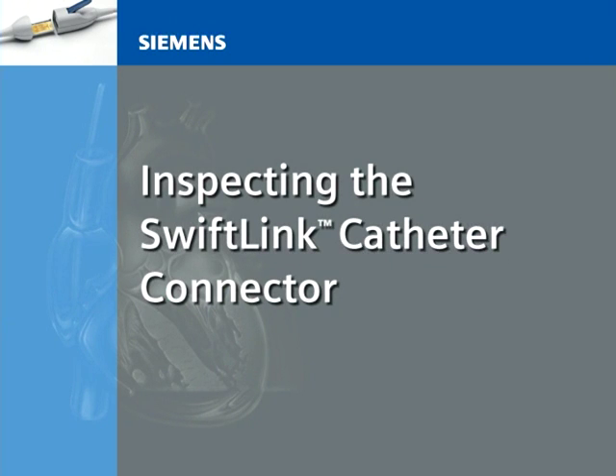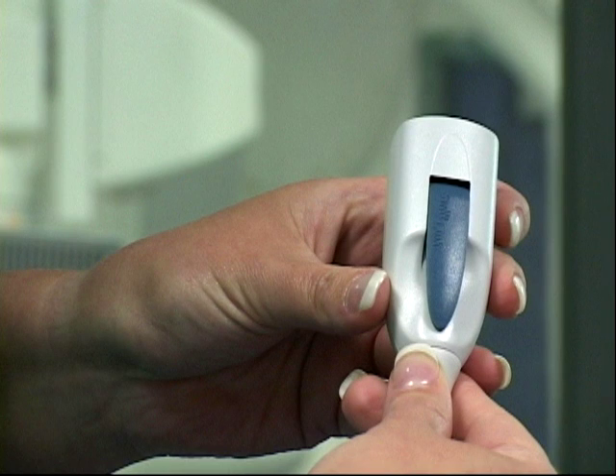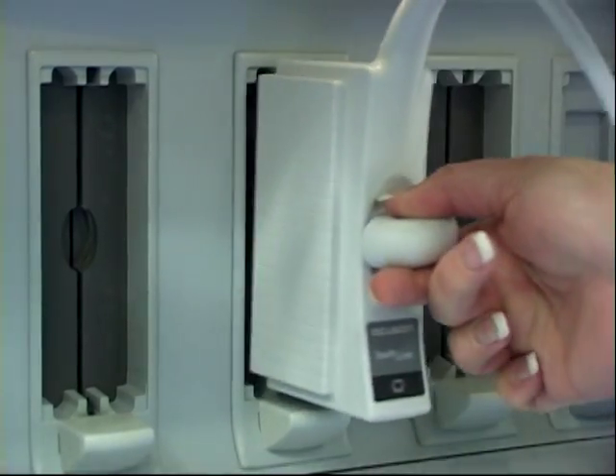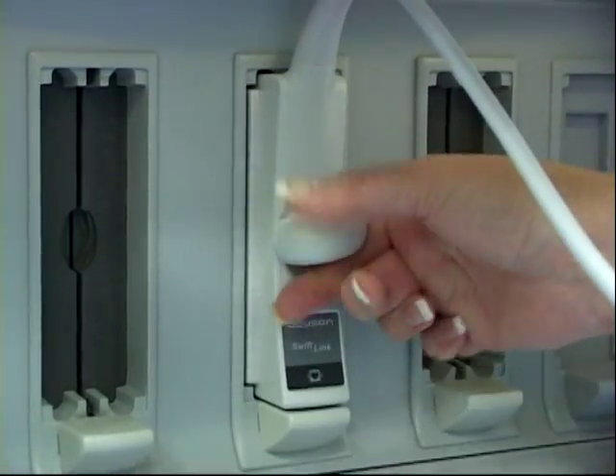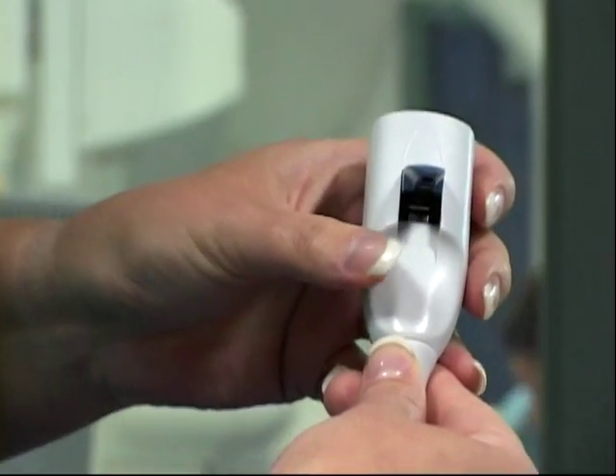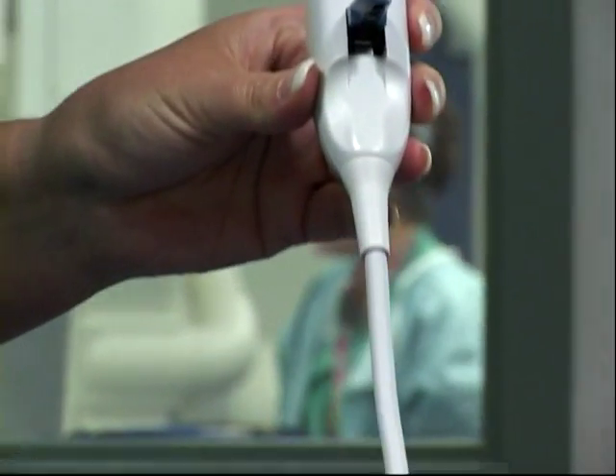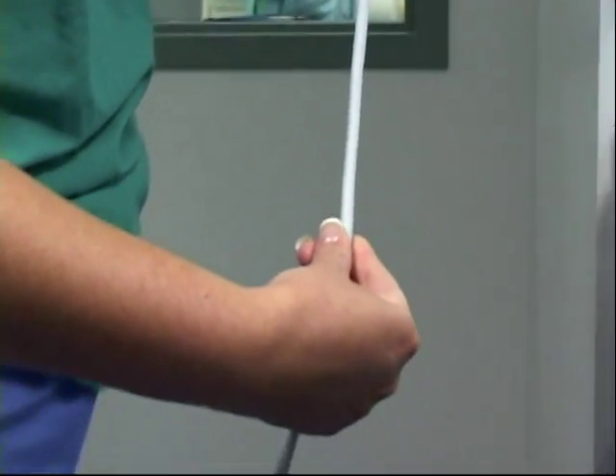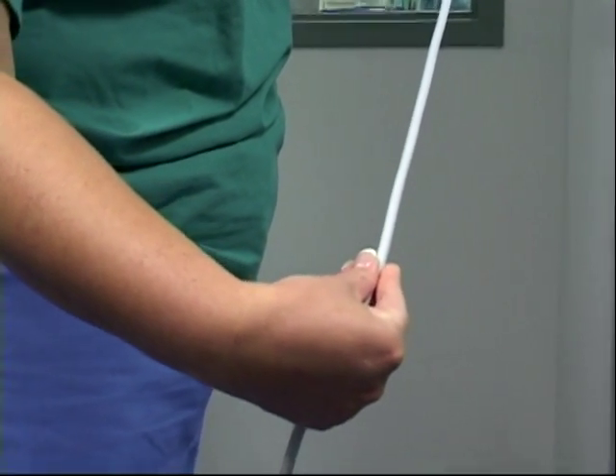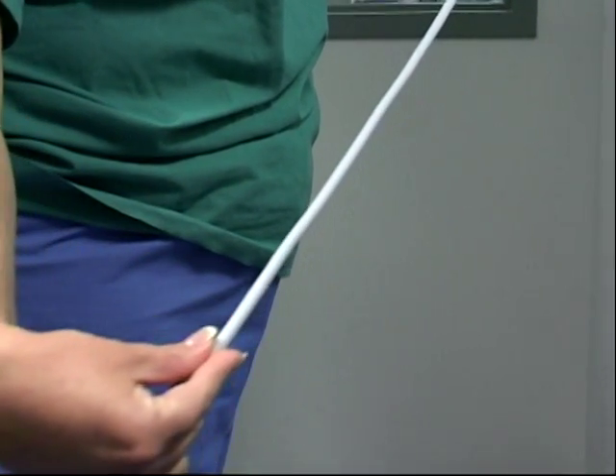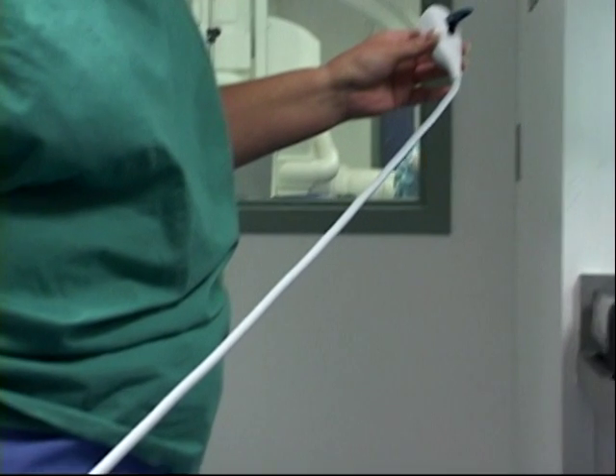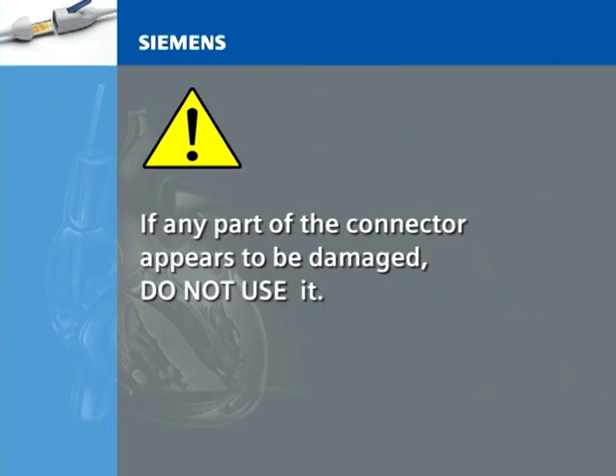Inspecting the SwiftLink catheter connector. The SwiftLink catheter connector is a reusable cable that connects the AcuNav catheter to the ultrasound system. Before connecting the SwiftLink connector to the ultrasound system, run your fingers along the entire surface of the handle, cable, and system connector, inspecting for any signs of mechanical damage. Ensure that the handle lever and the locking mechanism operate smoothly. If any part of the connector appears to be damaged, do not use it.